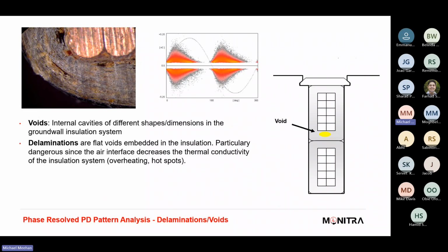PD will occur based on the AC wave. It will charge and discharge the voids, and those voids will charge and discharge based on that AC cycle. So PD is predominantly an AC phenomenon. It's not a DC phenomenon. I believe there is some research happening on PD in HVDC systems, but I think that's a fairly new field. From my understanding, most definitely it's a prevalent failure mode in AC systems.